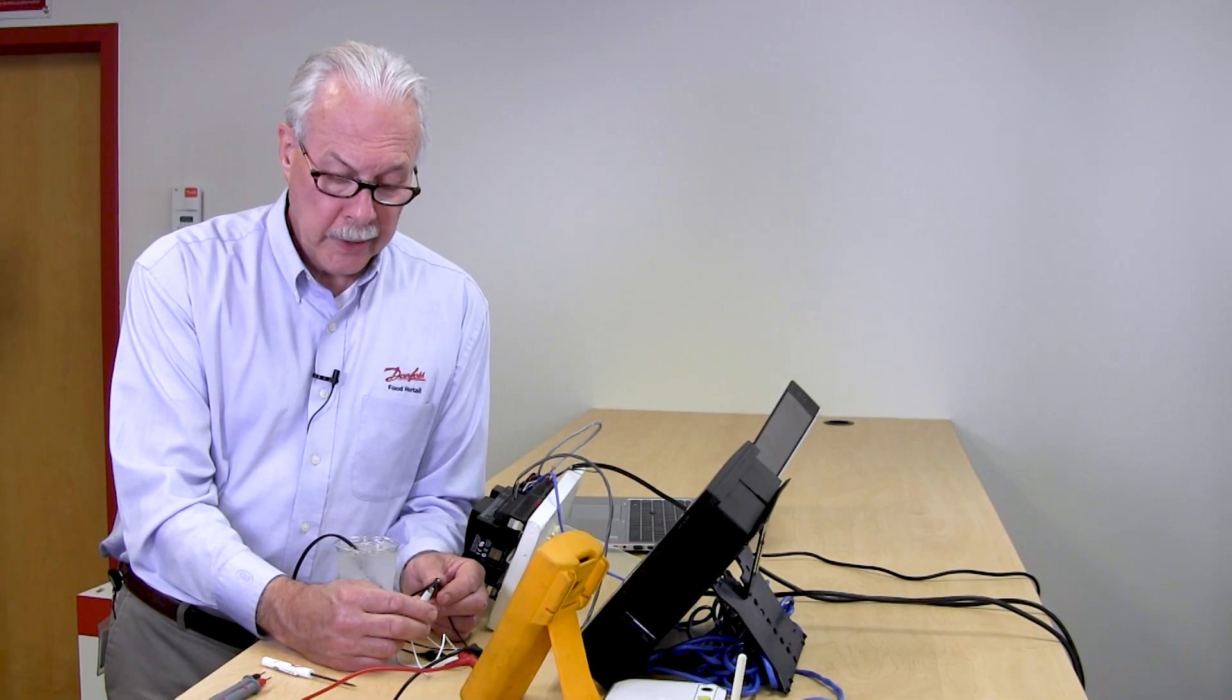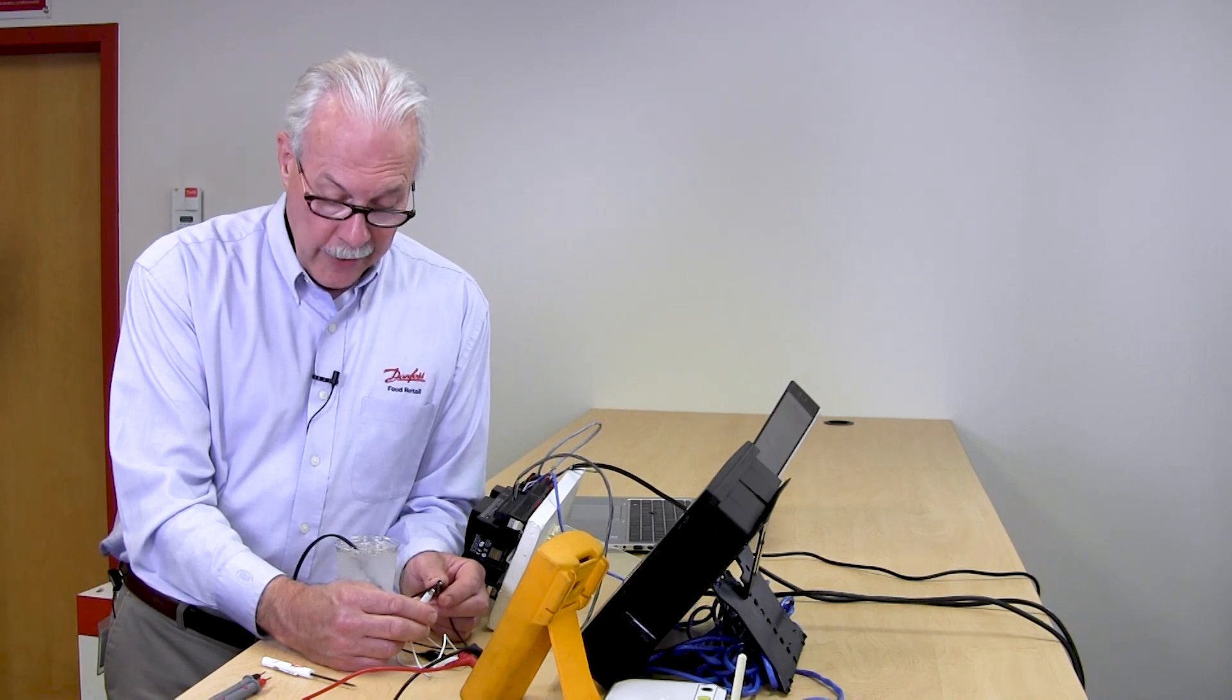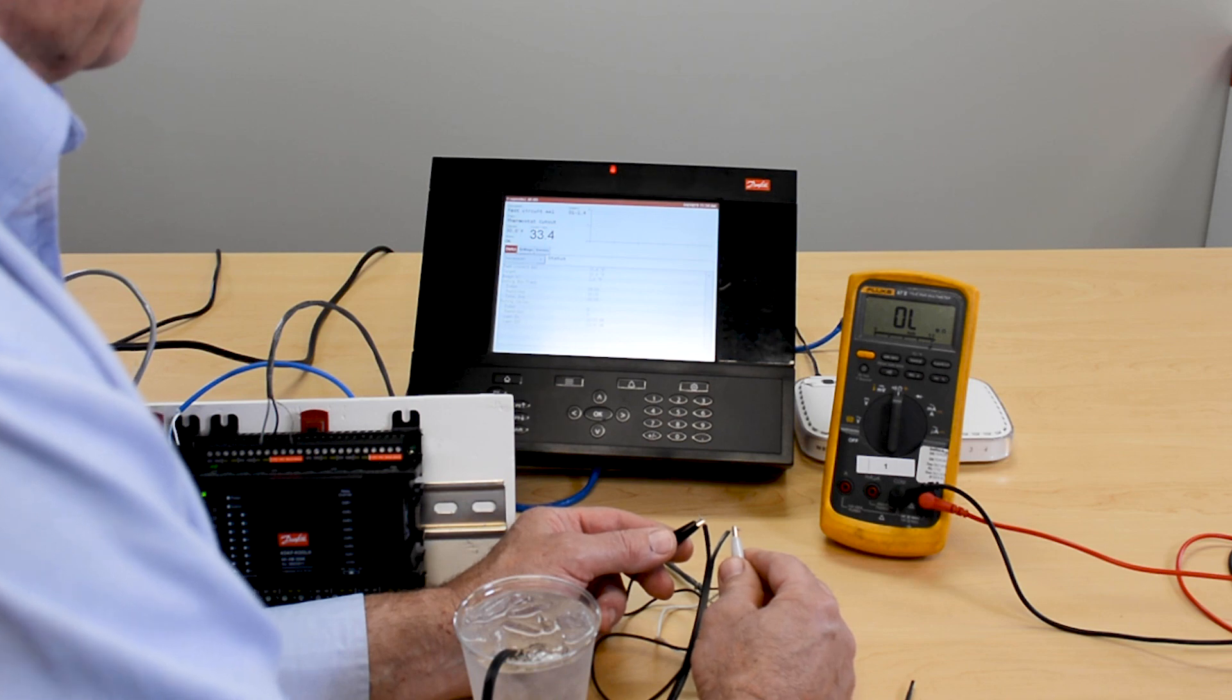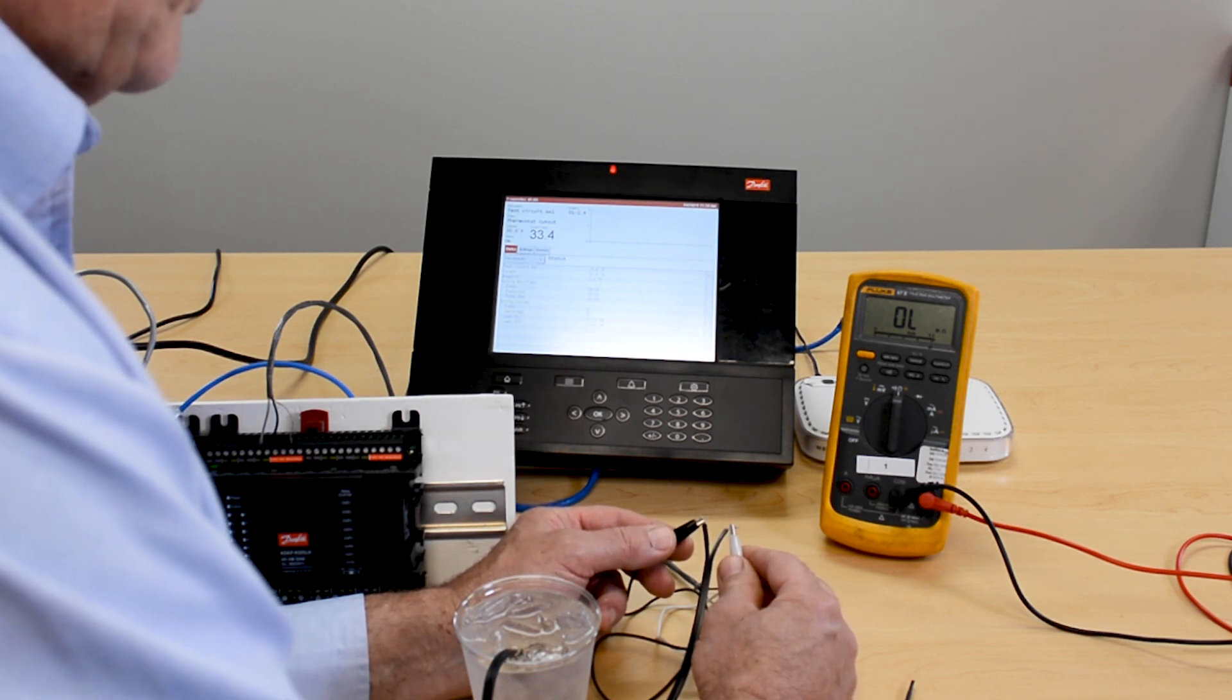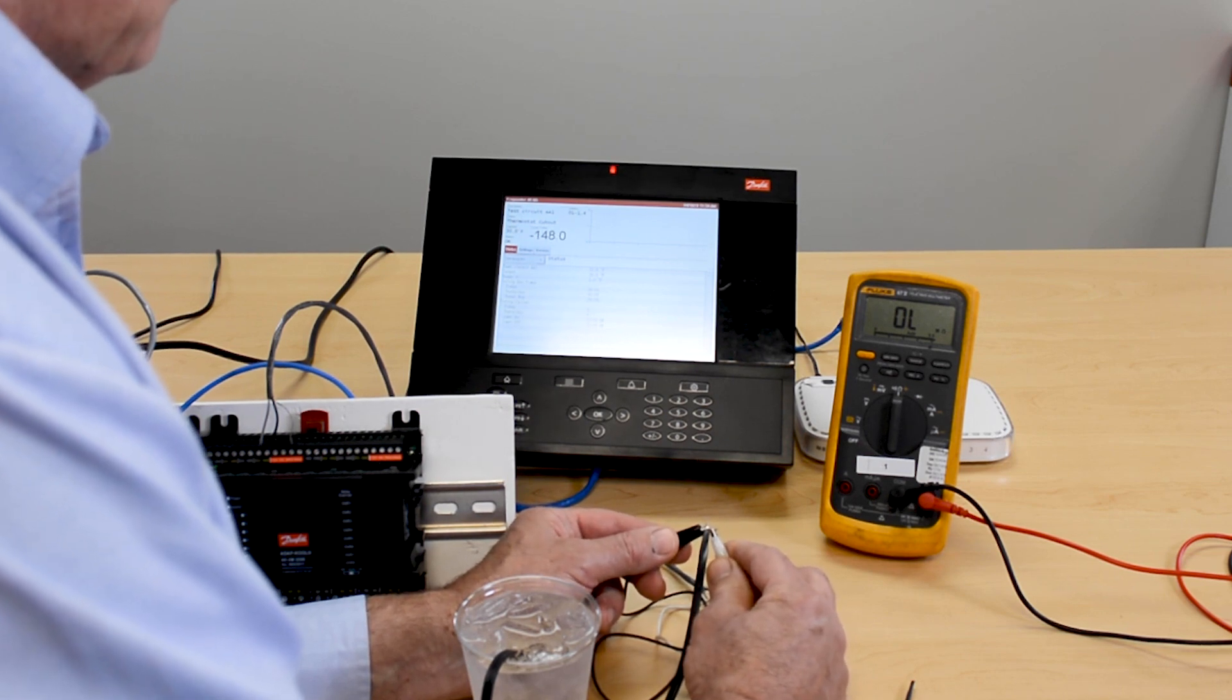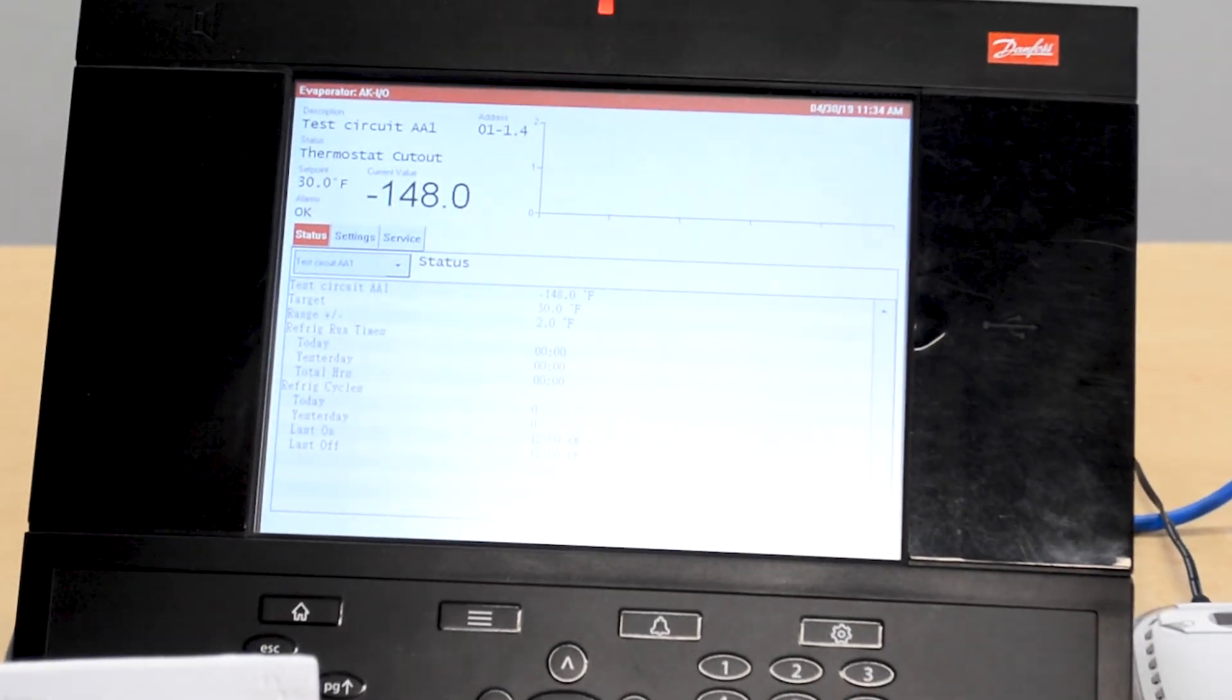Now we're going to look at the different scenarios for a temp sensor. As we have it right now in normal operating conditions, we can see on the display 33.4 degrees. But what is it going to show us if we have a short? I'll take these two leads and hold them together, and we notice it goes to minus 148.